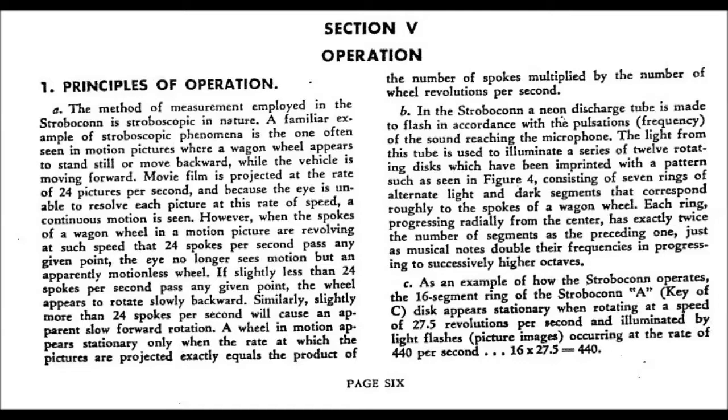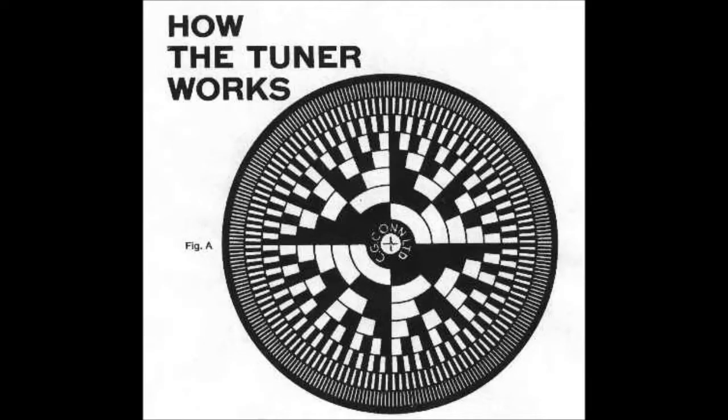Each ring progressing radially from the center has exactly twice the number of segments from the preceding one, just as musical notes double their frequencies in progressing to successively higher octaves. An example of how the Stroboconn operates: the 16-segment ring in the key of C. A disc appears stationary when rotating at a speed of 27.5 revolutions per second and illuminated by light flashes occurring at a rate of 440 per second. If you notice, the ratio of black to white on the disc doubles each ring from center to outside — 2 black spots in the center, then 4, then 8, then 16, and so on — corresponding to different octaves.